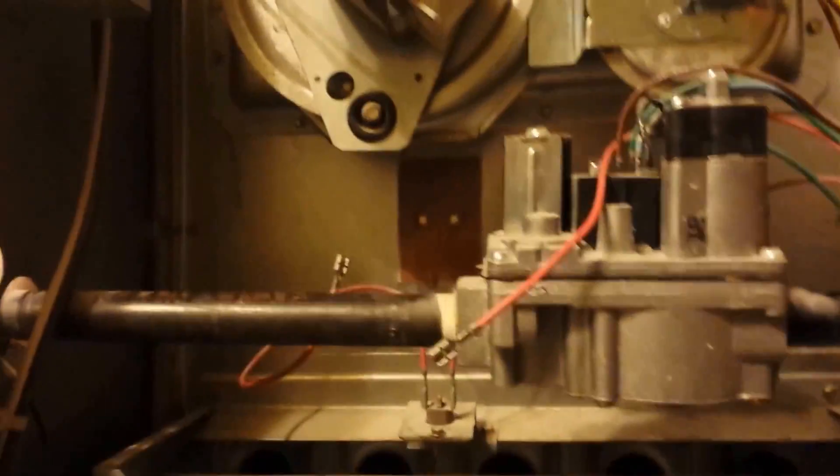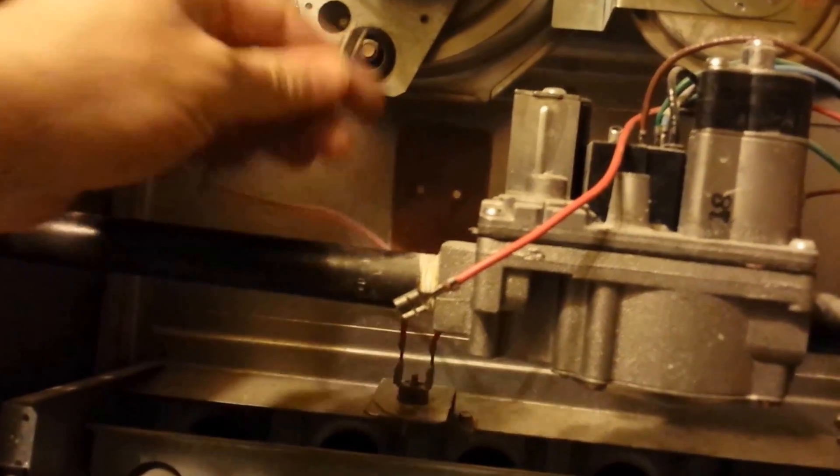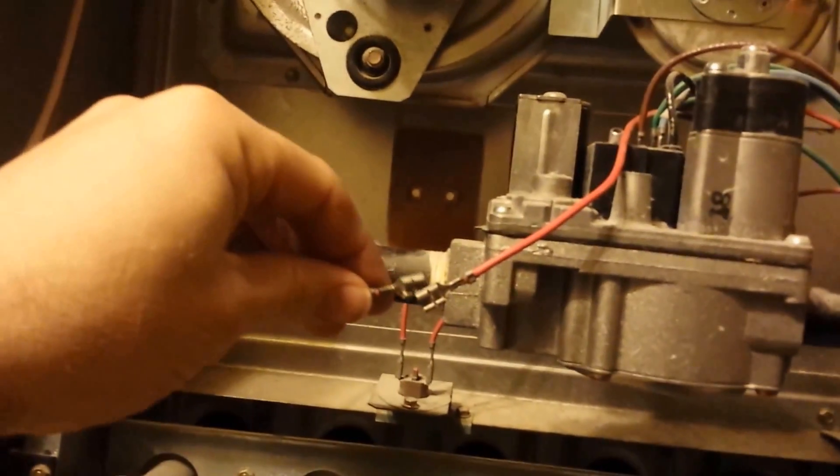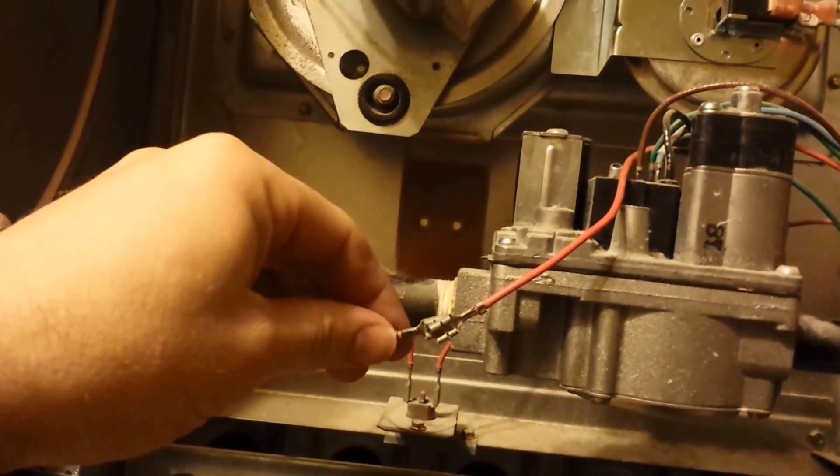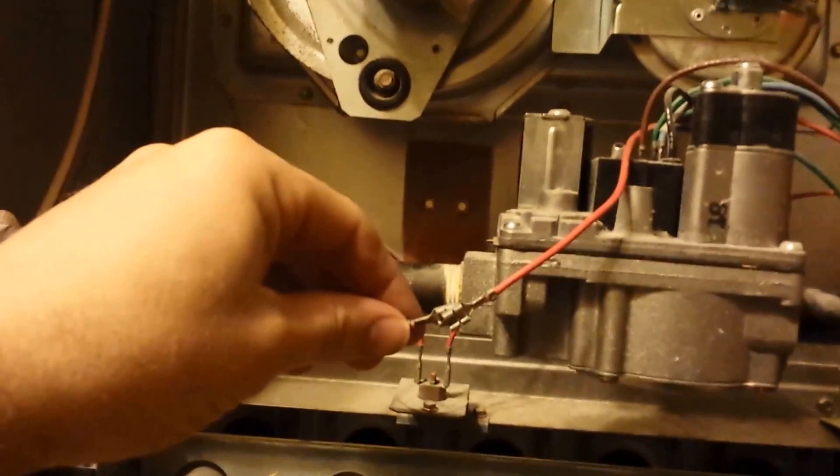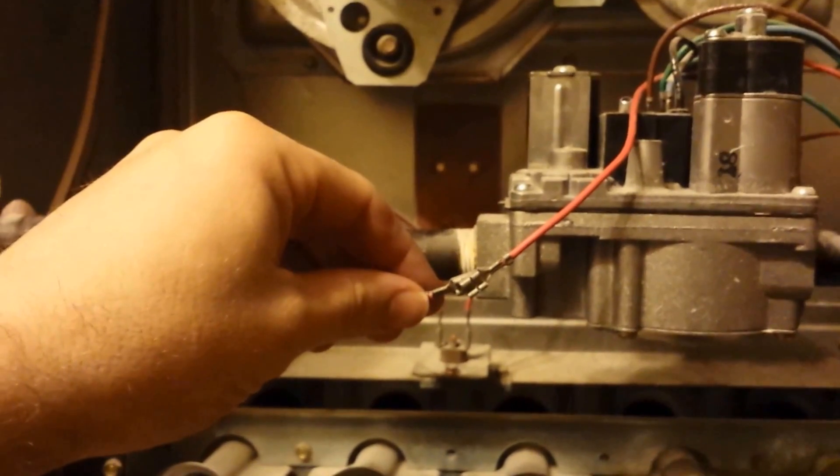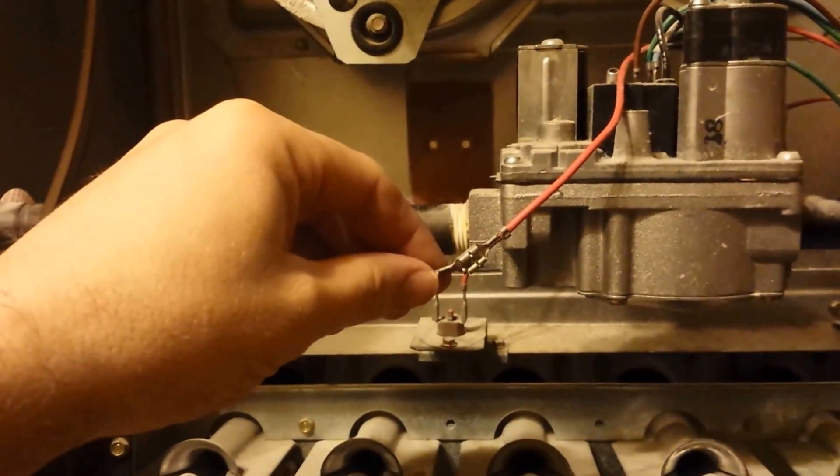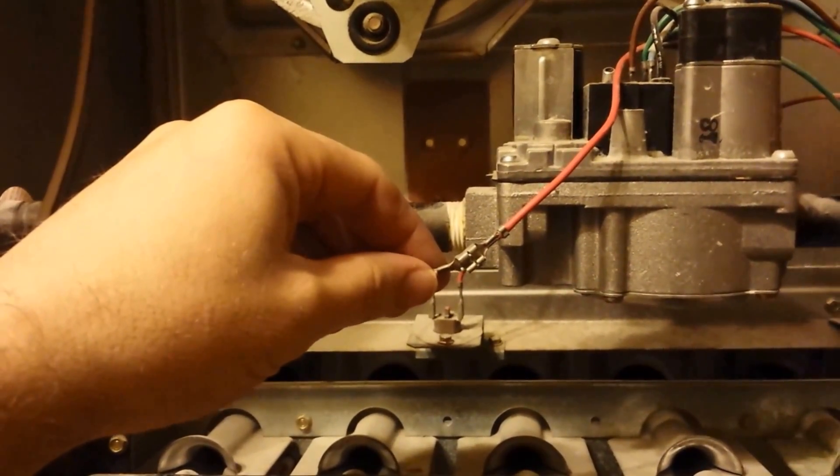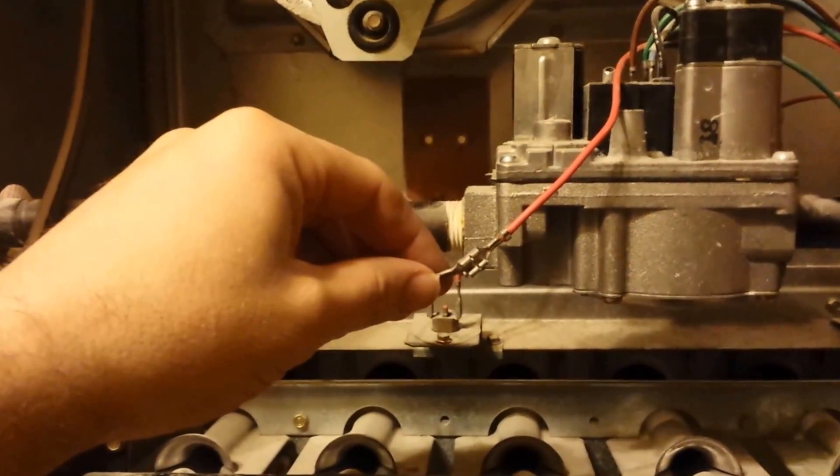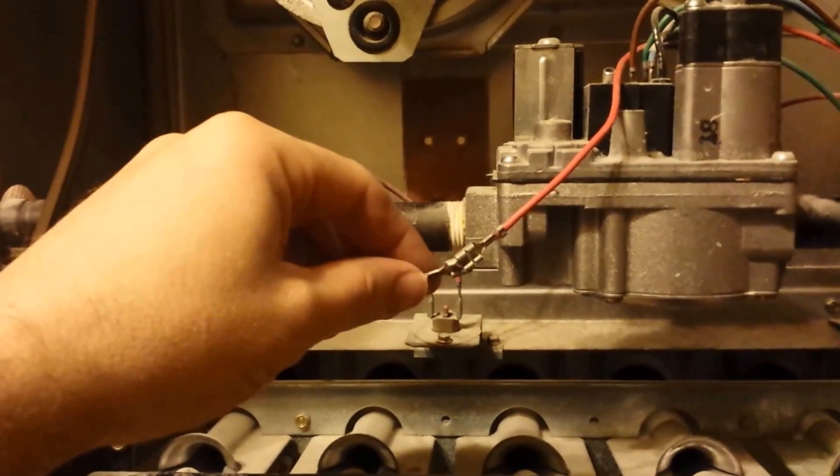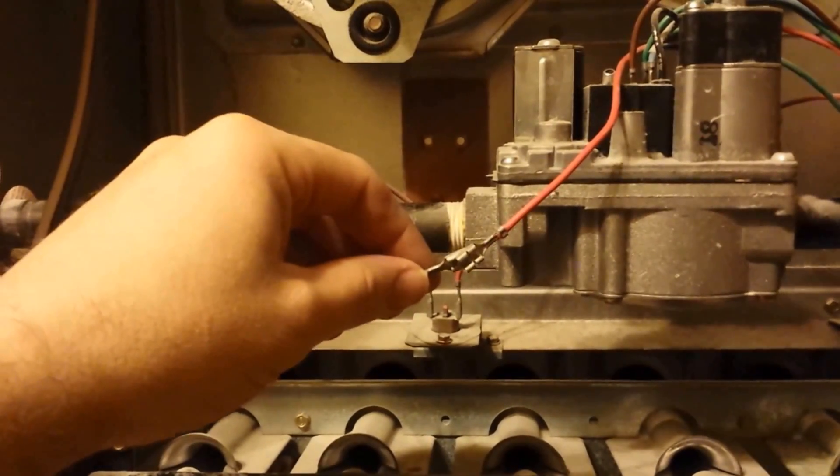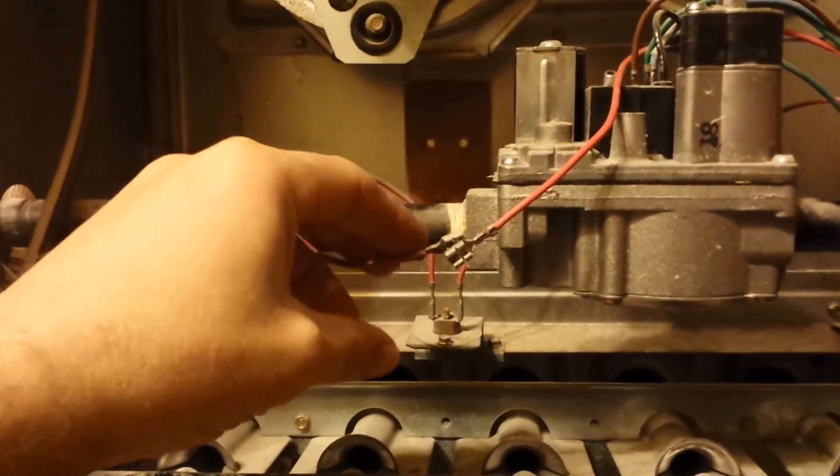So then what you can do is take these two wires and tape them together, and that if it will start up and then you'll get the flame ignite, you'll know by bypassing that switch that it's bad. So I'm going to go ahead and tape it up and I'll show you what happens.